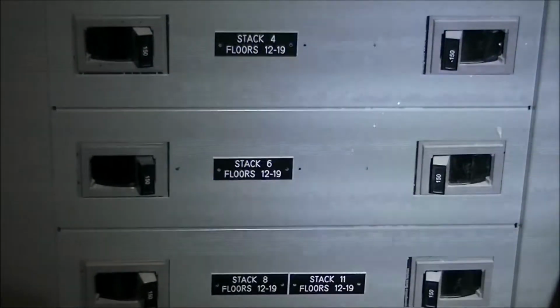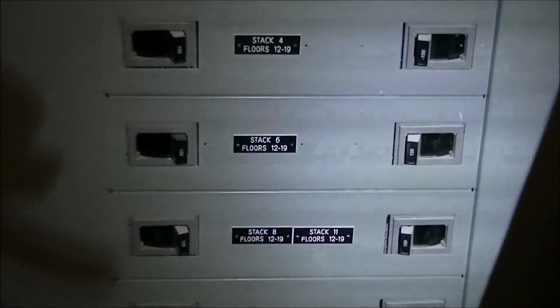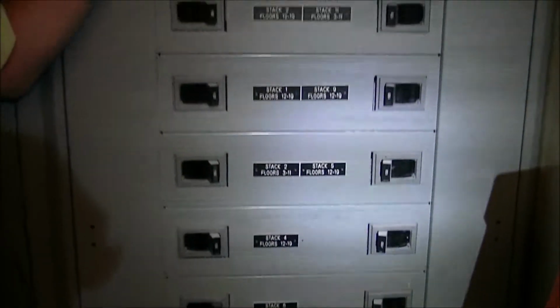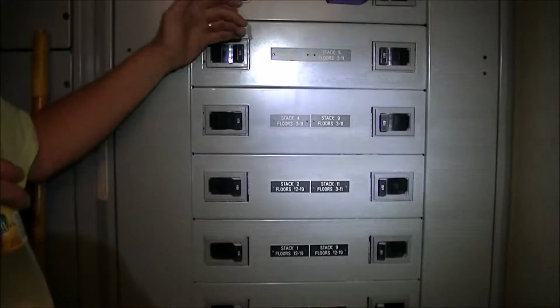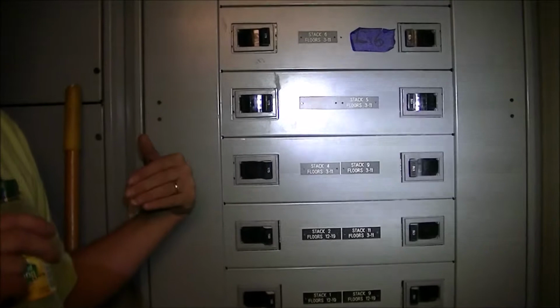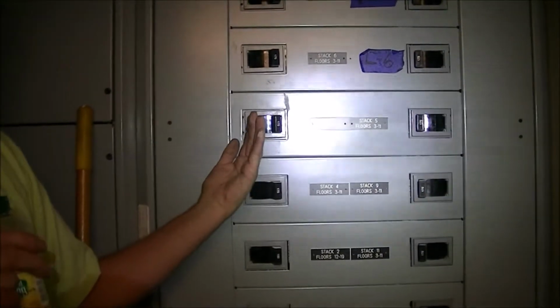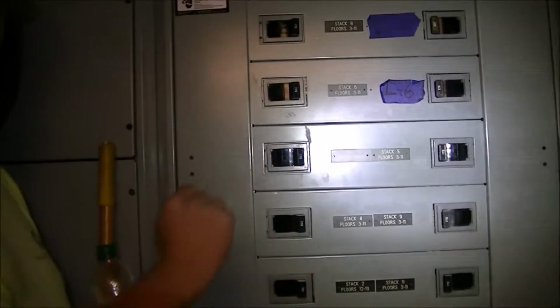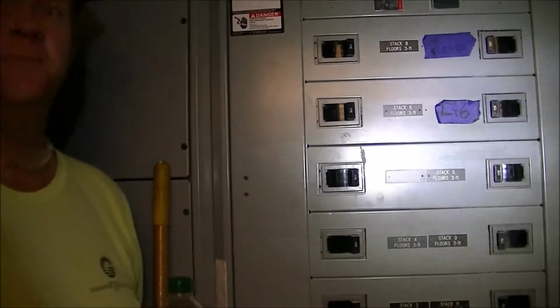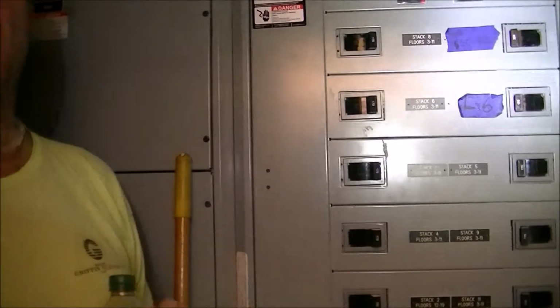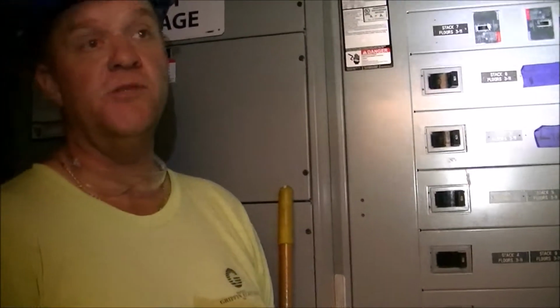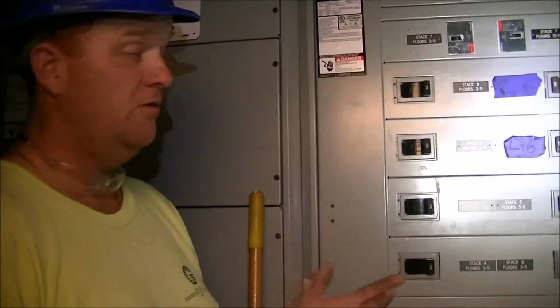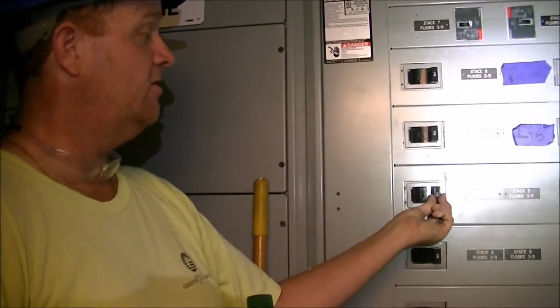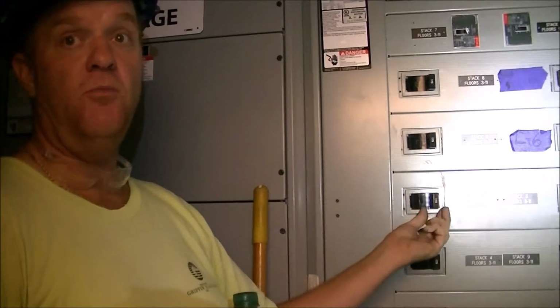One good note about these circuit breakers: you may walk in and think that's not tripped, but they don't go all the way back, they sit in a mid position. What you have to do is pull them off and then push them back on again. So at a quick glance you may think it's not tripped out, but it actually has. A telltale sign is if you grab it like this, it'll move backwards and forwards a lot more than that.